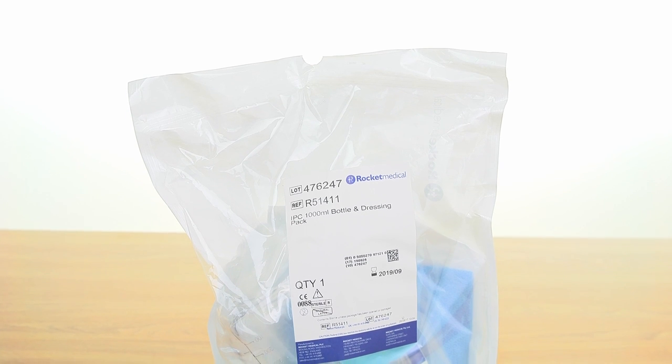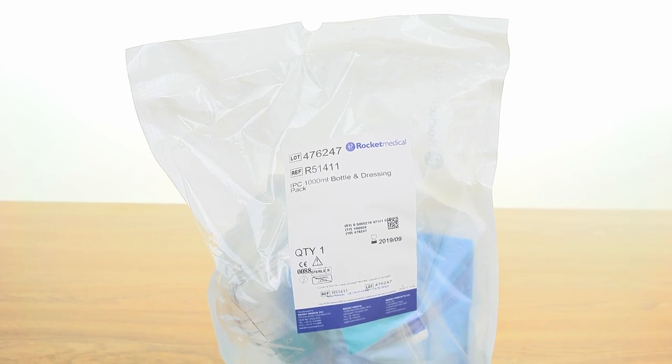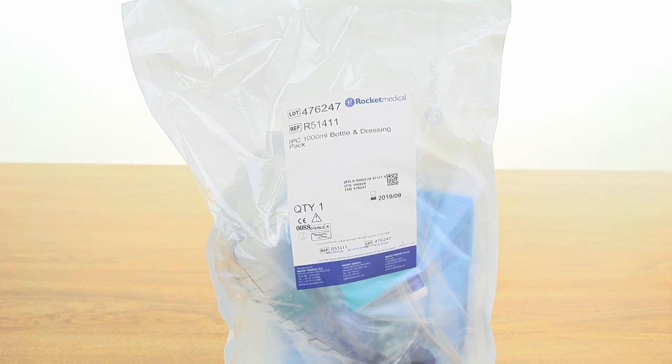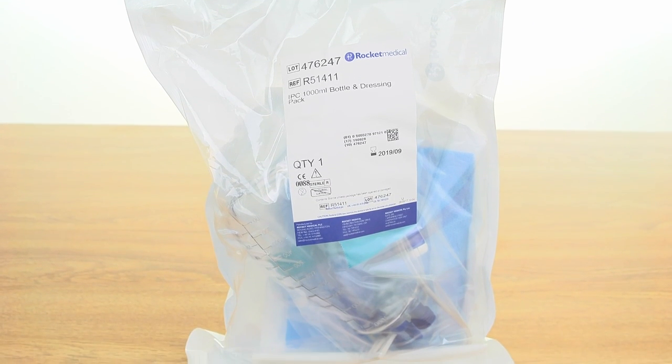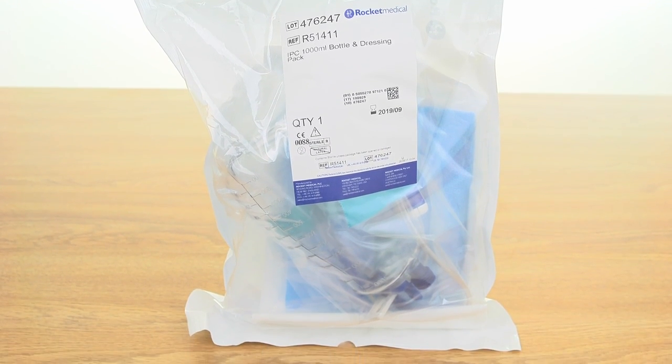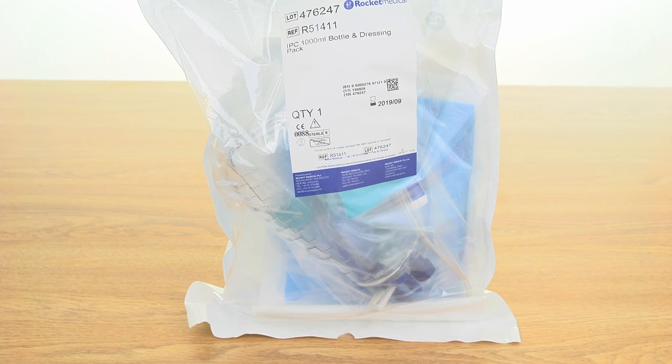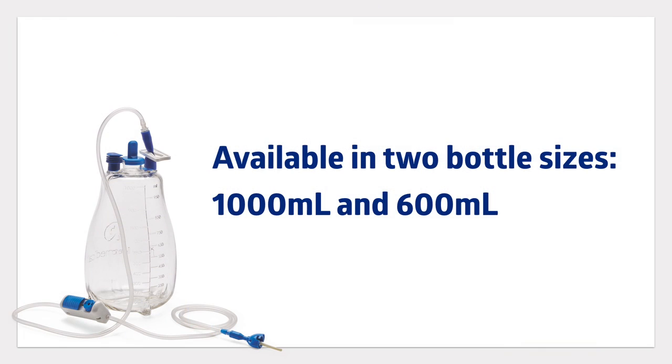The ROCKET IPC Pleural Drainage System comes packaged as a sterile kit, which includes everything you need to properly drain fluid, as well as instructions on how to use the ROCKET collection bottle. There are two bottle sizes available, 1000 milliliters and 600 milliliters. Both bottles work exactly the same, providing suction to drain the patient's pleural or peritoneal cavity.